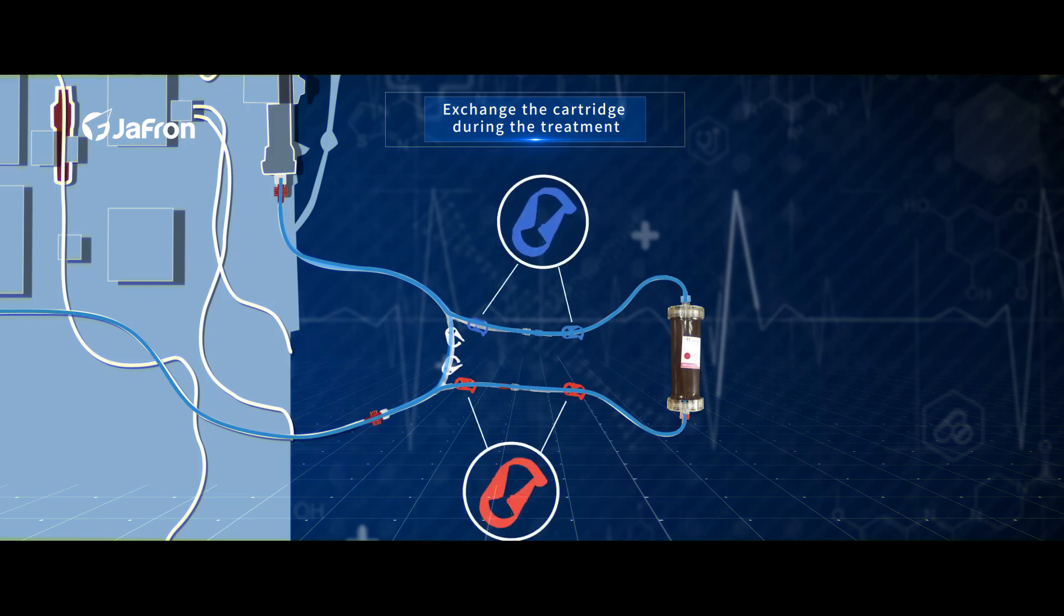Remove and discard the connected cartridge and replace with a new one. Open the blue and red clips, clamp the white clips, and continue the treatment.